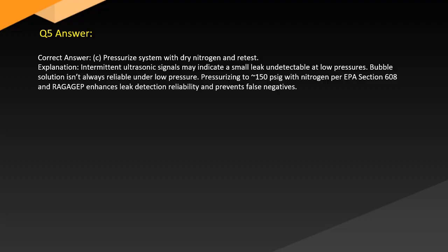Answer. Correct answer, C. Pressurize system with dry nitrogen and retest. Explanation. Intermittent ultrasonic signals may indicate a small leak undetectable at low pressures. Bubble solution isn't always reliable under low pressure. Pressurizing to 150 psig with nitrogen per EPA Section 608 enhances leak detection reliability and prevents false negatives.